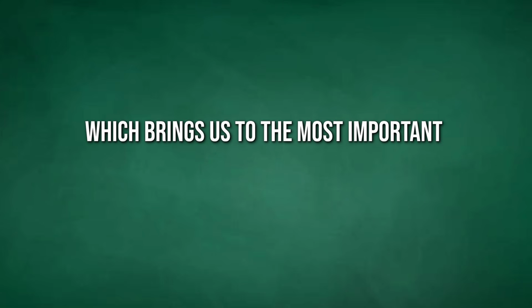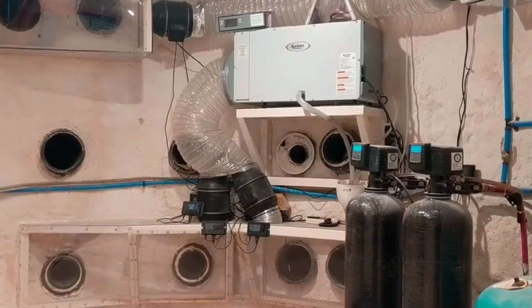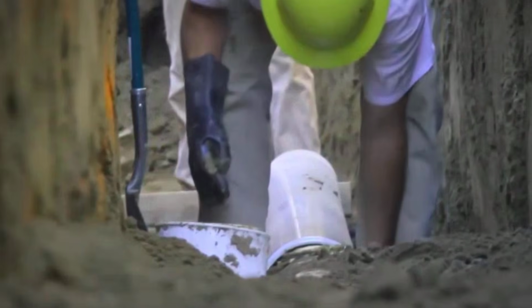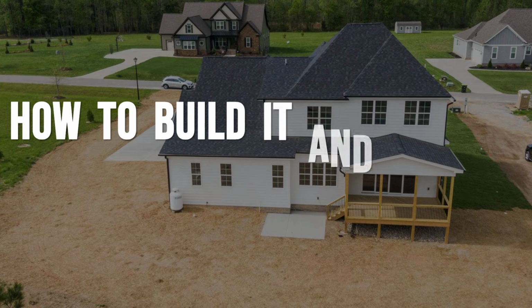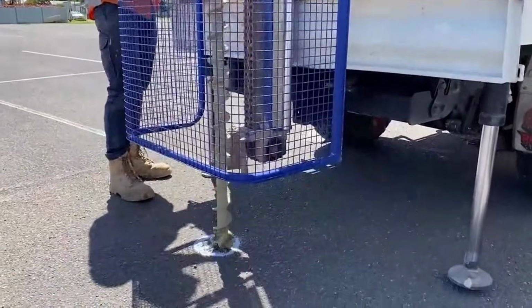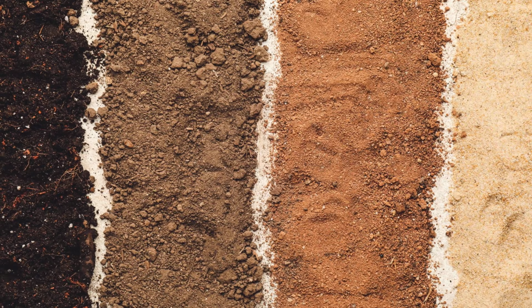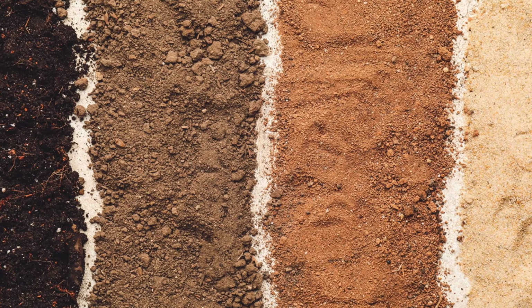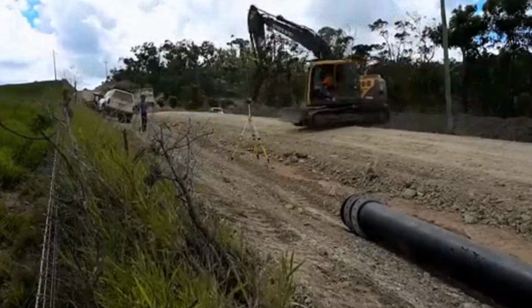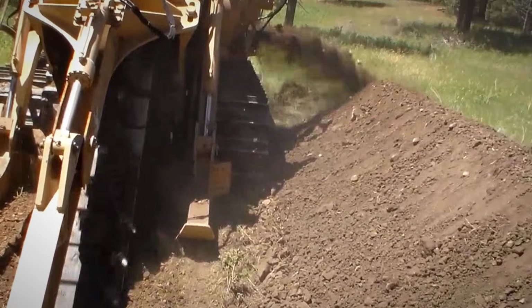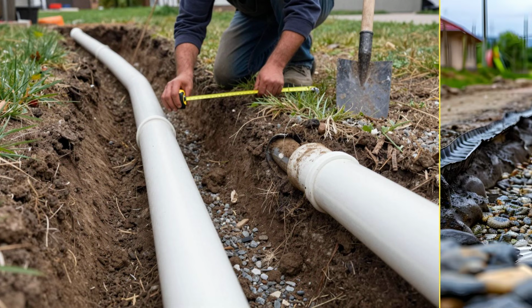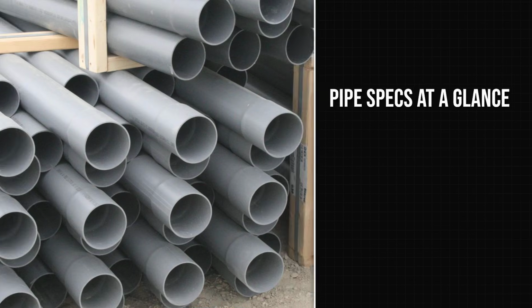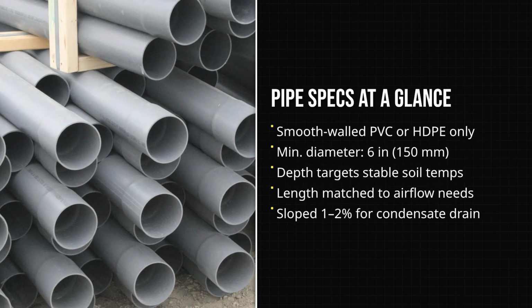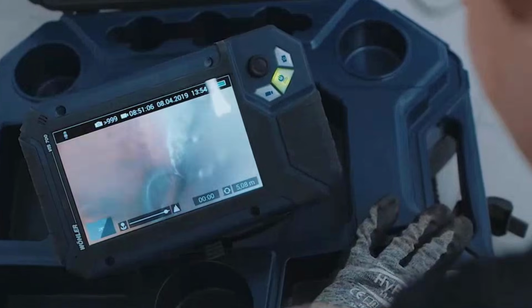Which brings us to the most important question. If this system is both effective and proven, how do you actually build one? The process begins with understanding your site. Soil type plays a critical role. Moist, dense soils like clay conduct heat more effectively than dry, sandy soil. Depth is equally important. The pipe must be buried at least 6 feet underground to reach stable temperatures. Shallower installations reduce effectiveness significantly. The pipe itself must be smooth-walled, typically PVC or high-density polyethylene, with a diameter of at least 6 inches. Corrugated pipes are avoided because they trap moisture and promote mold growth.